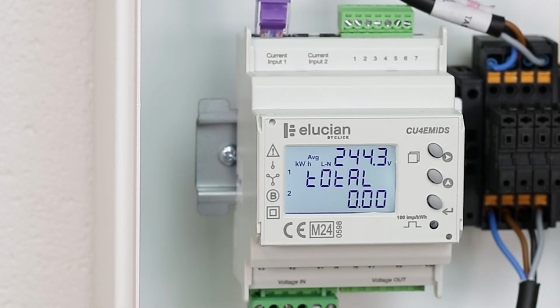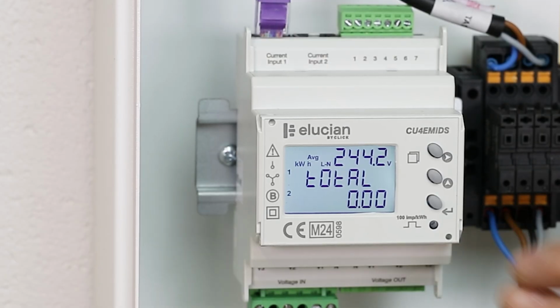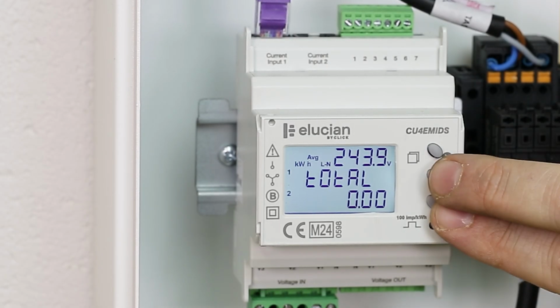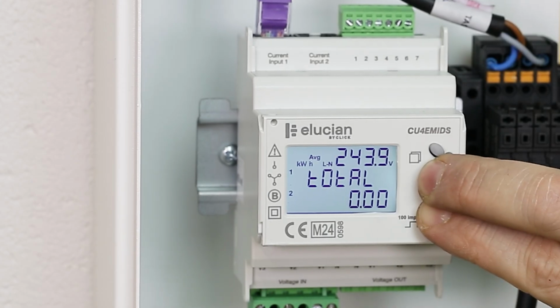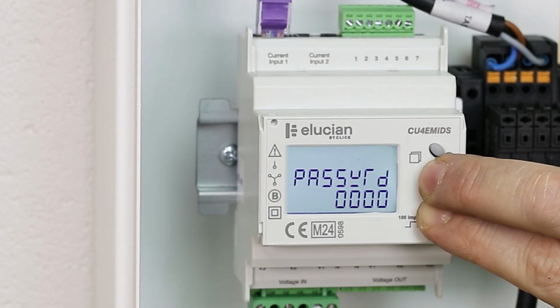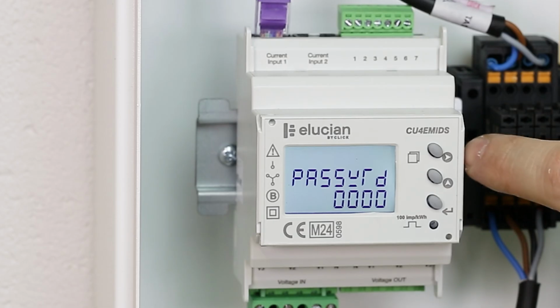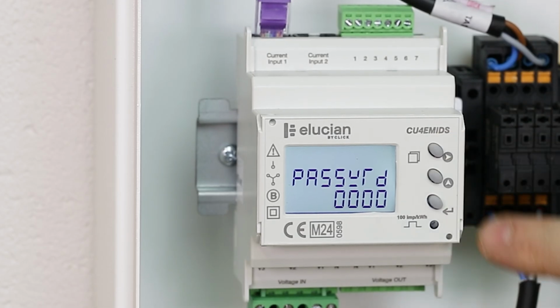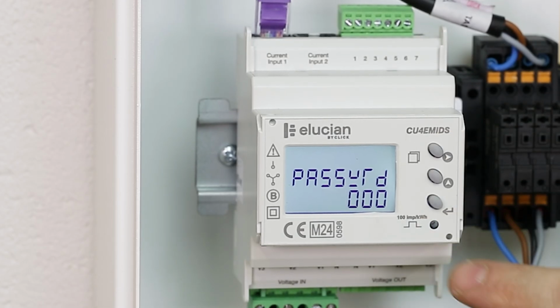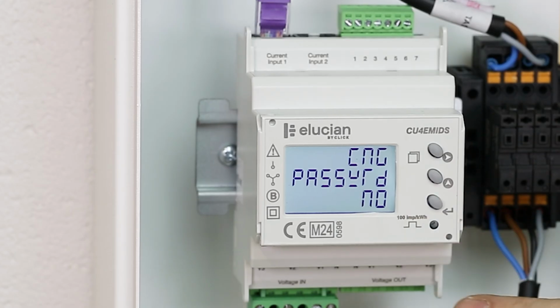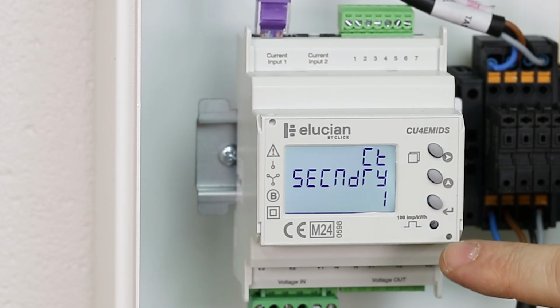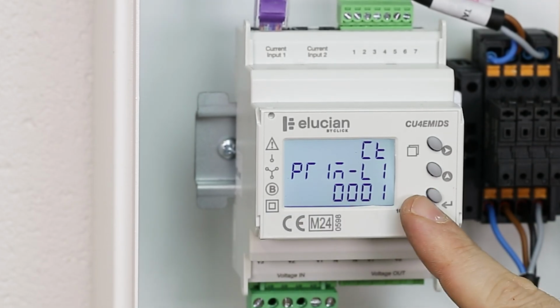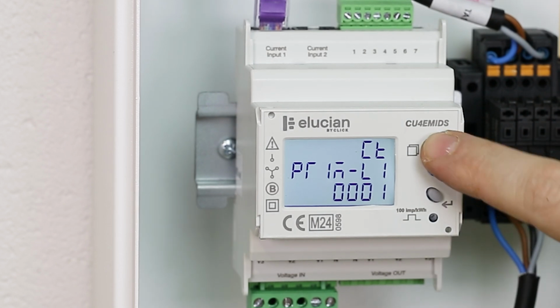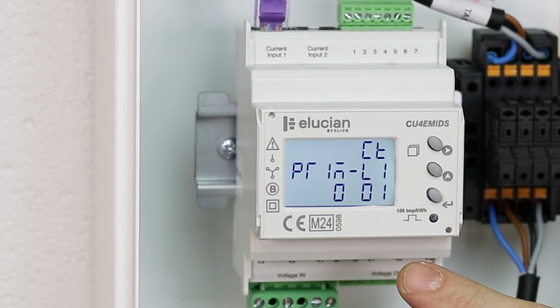To get into the settings to set up the meter, press and hold the lower two buttons together for 3 seconds. The default factory password is 1000. To set this, press the top button to activate the first 0 digit and press the middle button to change it to 1. Press the lower button to scroll through the settings menu and arrive at the CT primary L1 screen. Press the top button to toggle between changing each digit.